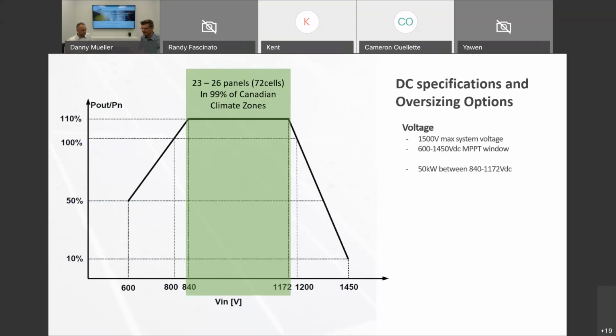But at the same time, when the ambient temperature gets hotter and your panel reaches much higher temperatures, for example 50, 55, or even 60 degrees Celsius, your input voltage to the inverter is still within the range where the inverter is able to output full nameplate power, and you're not going into that last segment where you have less power available just based on curtailment of the boost converter. There are some climate areas, for example, Southern Ontario, where we have customers who design with 27 panels, but to play safe with modern higher wattage panels, which typically have a little bit higher voltage per panel as well, 23 to 26 panels is a design which works in almost all cases in Canada.